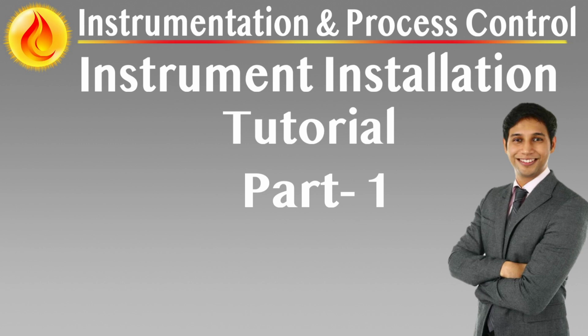Flushing, venting, and draining are essential aspects of impulse line integrity, not merely maintenance conveniences. Each connection must serve a clear purpose, be resistant to tampering, and eliminate environmental or personnel exposure risks. By prioritizing mobile solutions, self-contained flushing circuits, and intelligent isolation techniques, the system maintains operational safety while reducing long-term maintenance burdens and regulatory concerns.